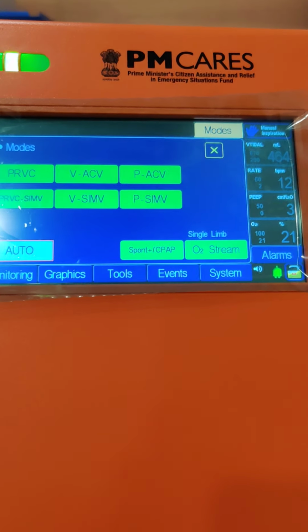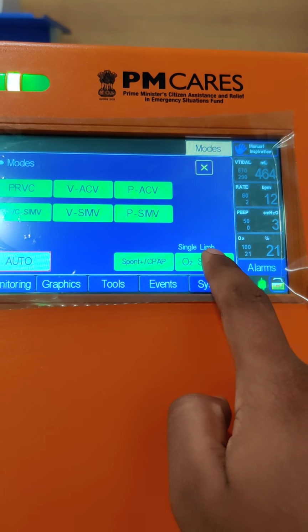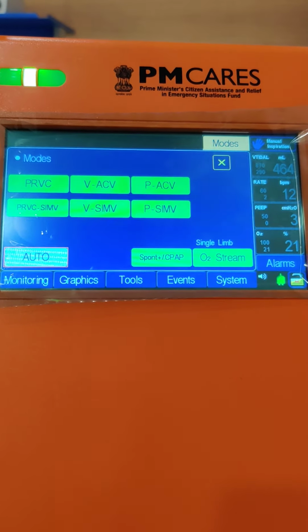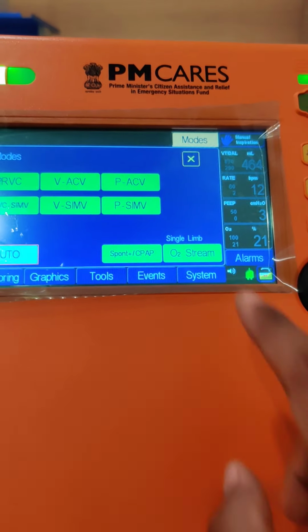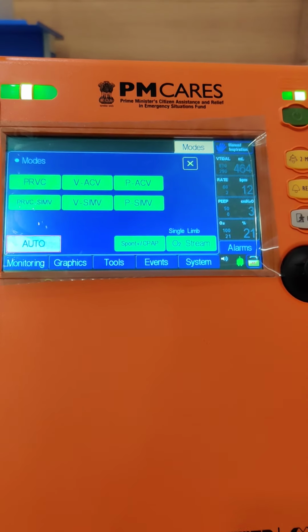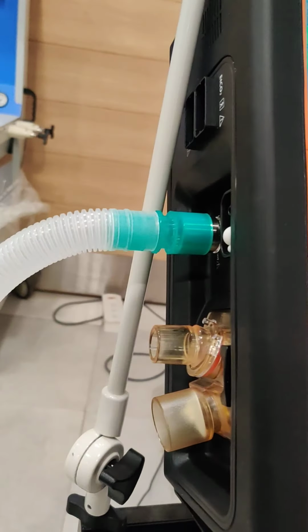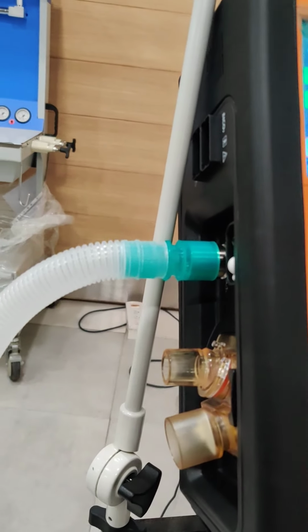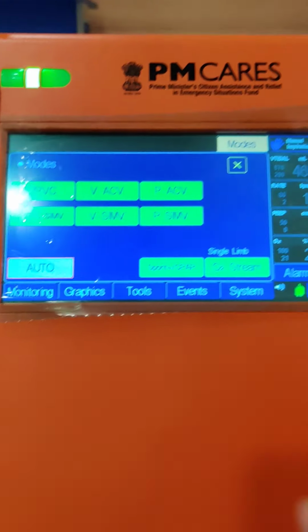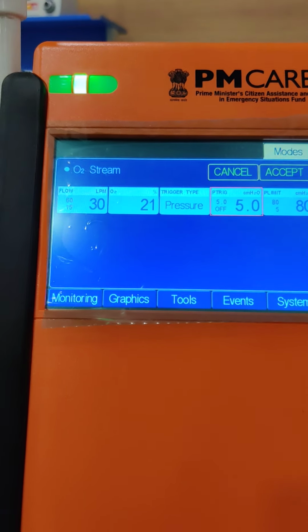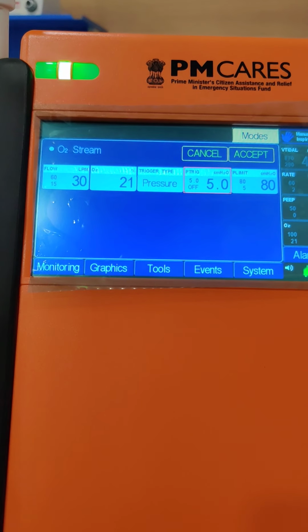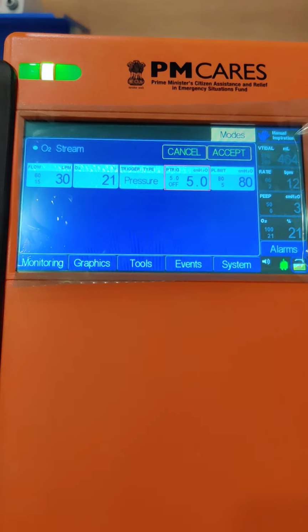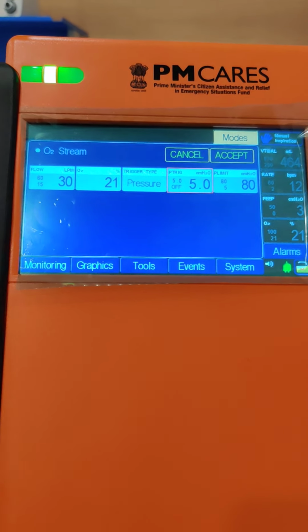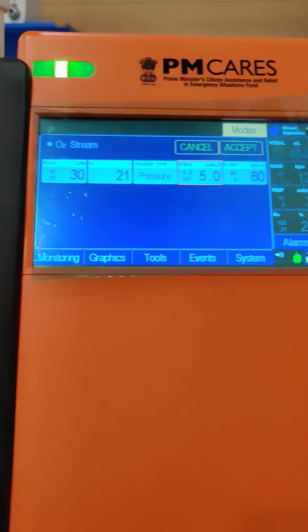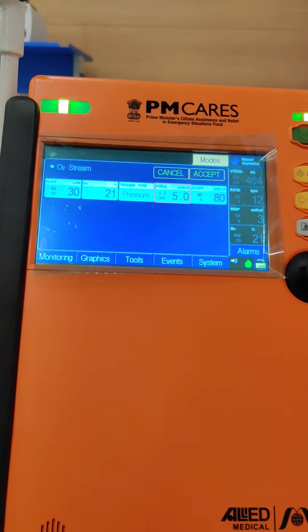Now coming to the last mode of ventilation, that is O2 stream. So here, as you can see, it is mentioned single limb. This mode of ventilation will run only with the single limb circuit. So I have connected a single limb circuit over here, and I have removed the expiratory limb from here. In this mode of ventilation, it is high flow nasal cannula therapy only. On the front of the single limb you have to connect the nasal prongs that are available with us and are also available in the market.